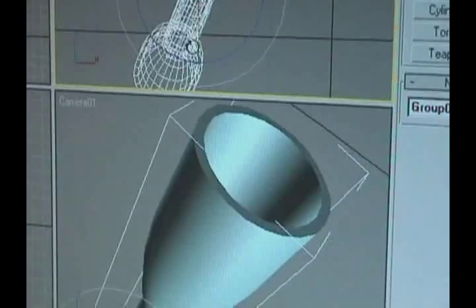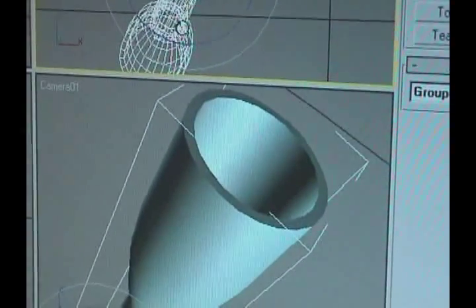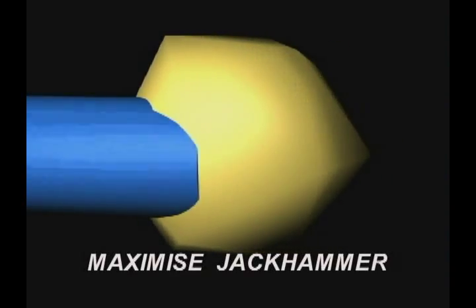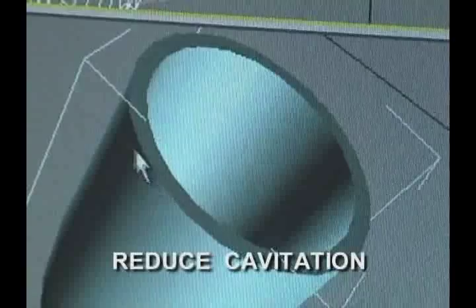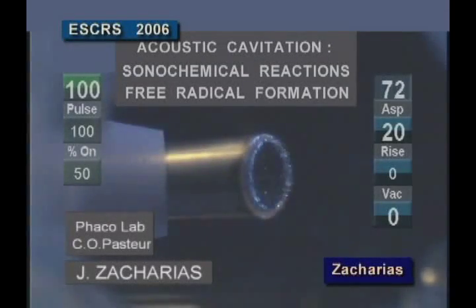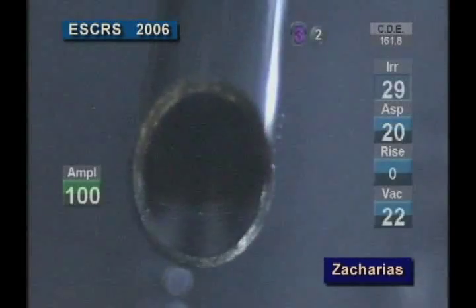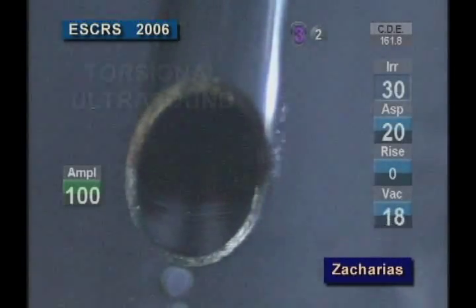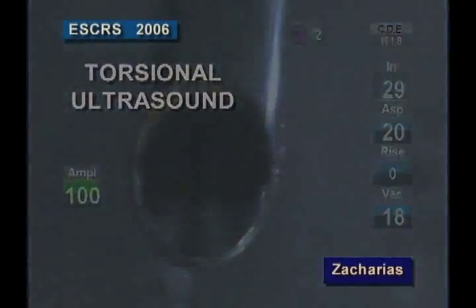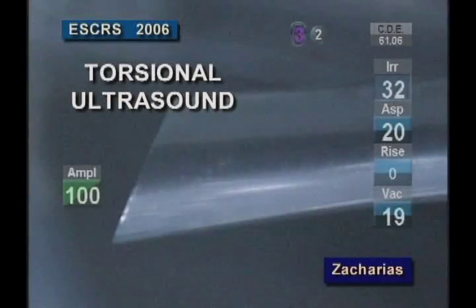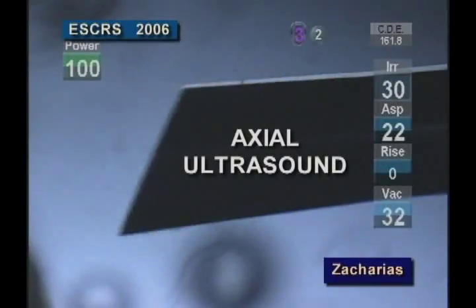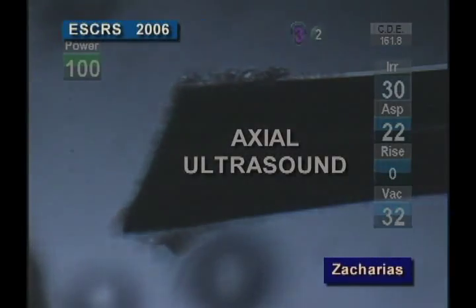With this in mind, technology should be focused on maximizing the jackhammer effect and reducing the cavitation effect, which does not assist in lens emulsification and can potentially have a negative impact. In this direction, the recent introduction of torsional phaco produces effective lens disruption with almost no cavitation compared to axial phaco emulsification.